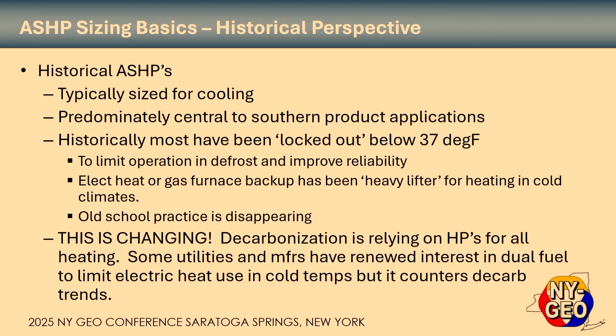Electric heat or gas furnace backup has been the heavy lifter for the heating side, with most of that product in cold climates. And that old school practice probably is disappearing more and more, but it's still fairly prevalent. Decarb is relying on these heat pumps for all of the heating. And so some utilities and manufacturers have renewed interest in dual fuel to limit the electric heat use at those cold outdoor temperatures.